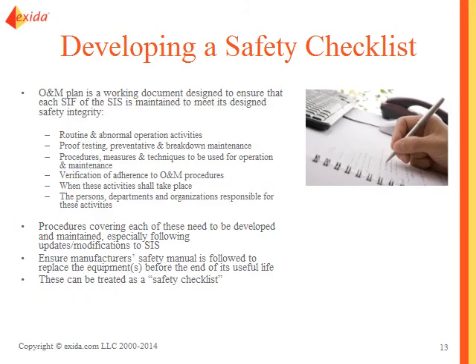Developing a safety checklist. The operation and maintenance plan should be a working document, designed to ensure that each SIF of the SIS is maintained to meet its safety integrity targets. This would involve having routine and abnormal operation activities documented, the proof testing, the preventative and breakdown maintenance, procedures, measures and techniques to be used for operation and maintenance.